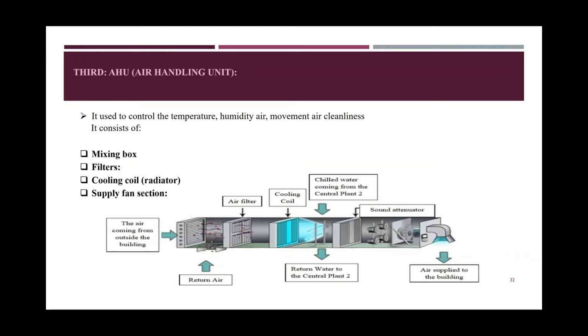The second element is a filter. Filters are to remove particles and contaminants of various sizes from the air. The third element is the cooling coil or radiator. Cooling coil is used to cool and dehumidify the air. These coils are arranged in rows with different fin spacing. Aluminum fins and copper tubes are used in the design of the coil. The corrosion resistant hydrophilic fins are also used due to their lower cost and lower resistance to the air velocity. The supply fan section: a centrifugal fan is used to circulate the air to the various parts of the building by using a motor.